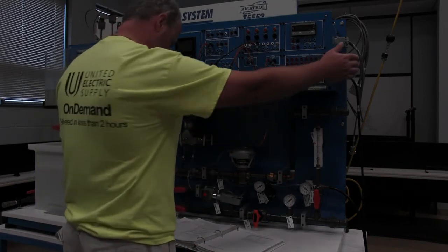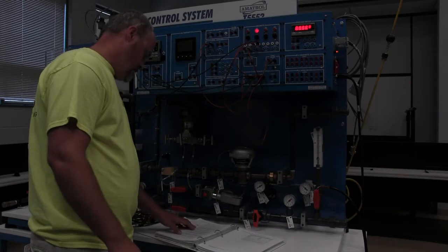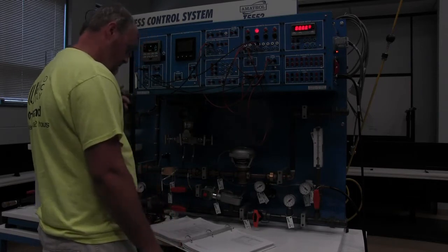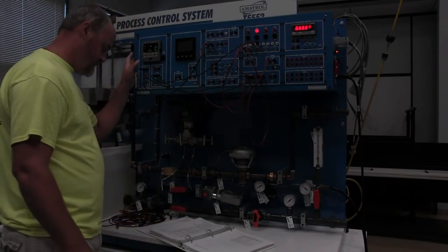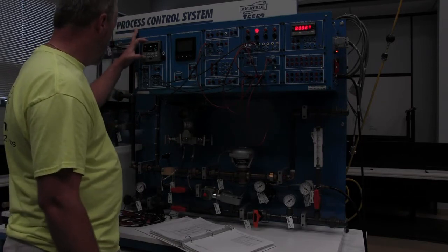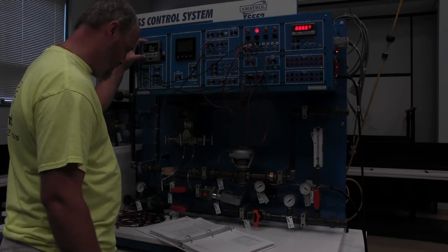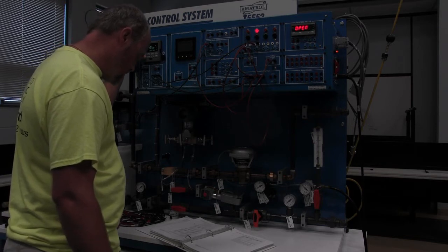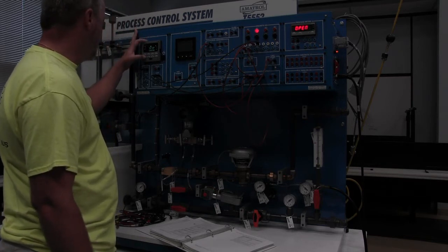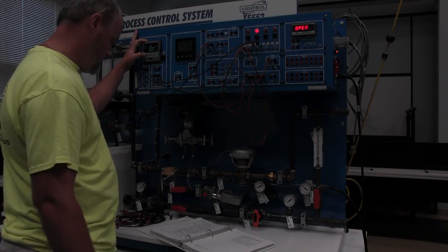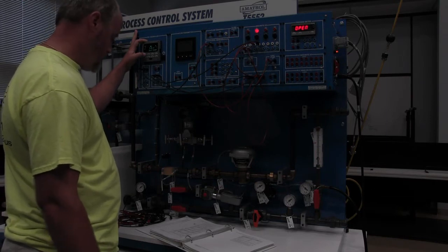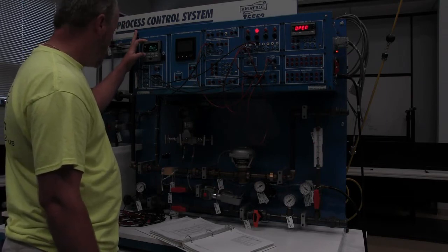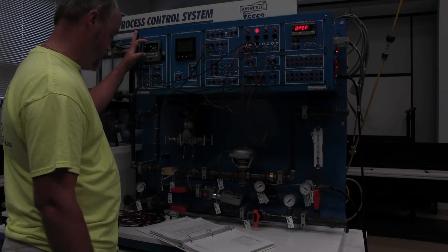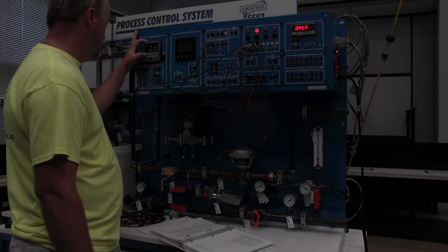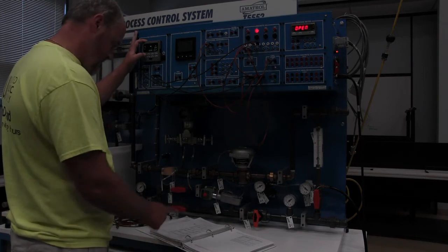So we're all hooked up. We're going to turn the power on, and we're going to set this controller up based off of the new set points. We're going to go to setup, where the first thing we're looking for is type 1, input 1, so 1 to 5 volts, transmitter is linear, high is 27.7, low is 0. Our bias is a little different, so we're good to go there.